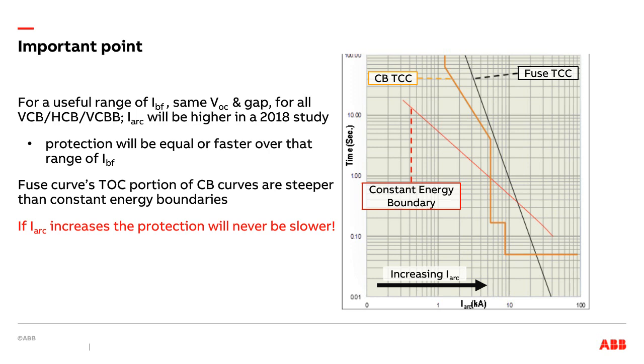Now, you may be getting a little higher energy than you actually would like to get, but you're being conservative. If you use too small a gap, you are shifting your protection on the left of this curve. And if you're shifting a millimeter in this area or a millimeter in here, it may not be a big issue. But if you're shifting from here to here, that's a big issue. You don't want to do that. So it's more important to be conservative in arcing current, which means you want a low arcing current. So if you're going to be potentially operating in this portion of the curve, handle it appropriately. Shift your short time setting to the left, do whatever you need to do. But you don't want to think you're here and then find out, oops, I'm actually here. That would not be good.